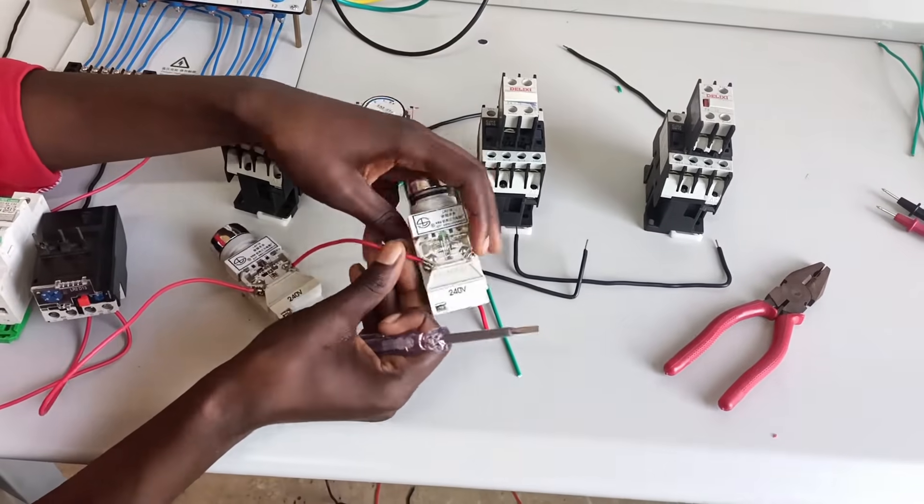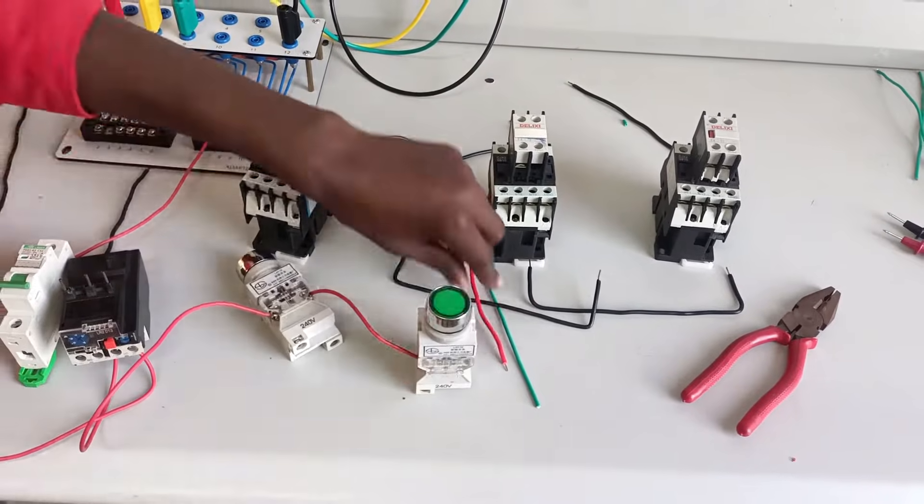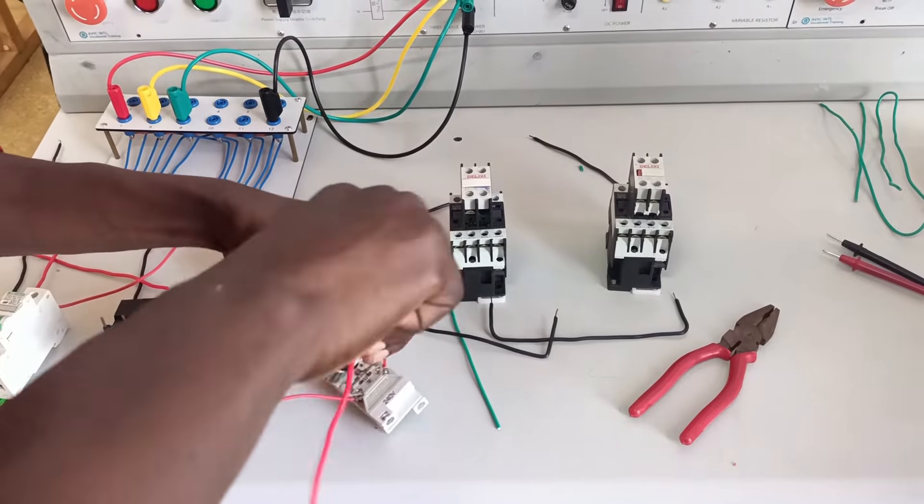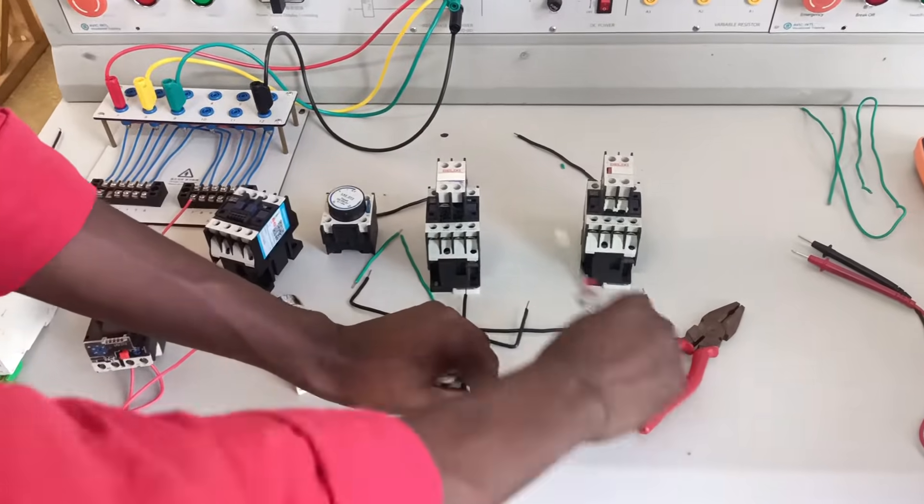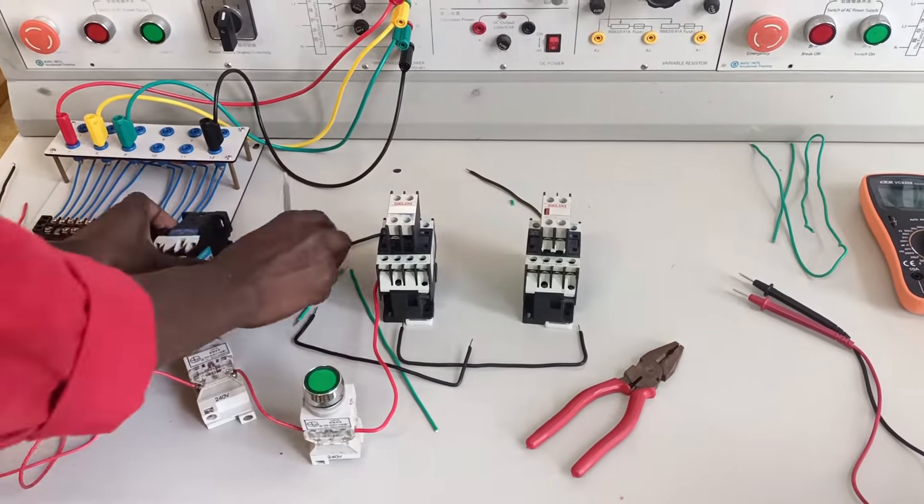For this case I'll terminate pin 3 of the NO push button loosely, but I'll need to terminate it again with another holding cable that will come from normally open terminals of the main contactor, that is pin 14.